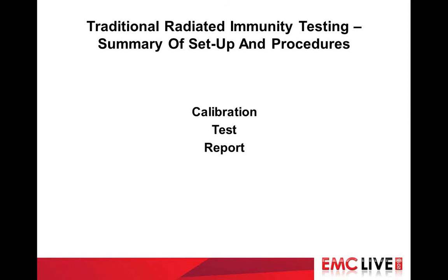The test is broken into 3 functions. Calibration. This is to be performed at least once a year, or if the test setup has been modified. Test, using 1 frequency tone. Test report, created in graphical or tabular format.